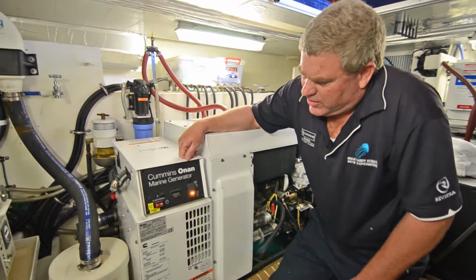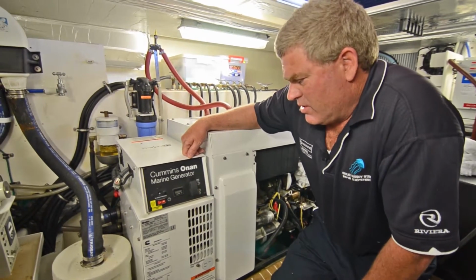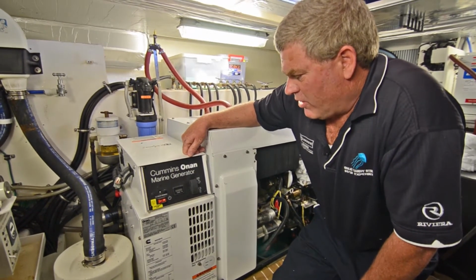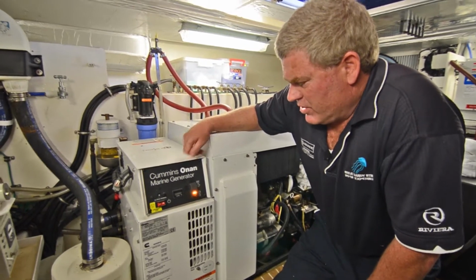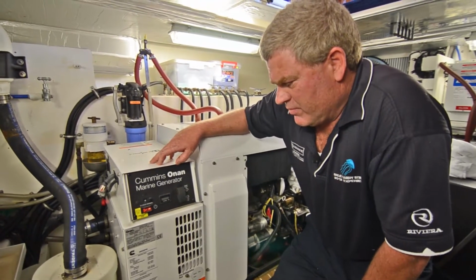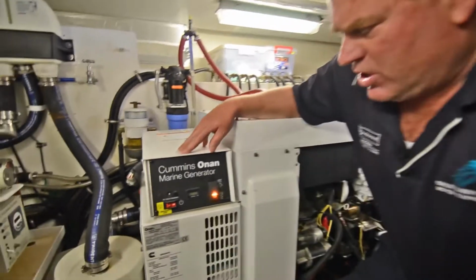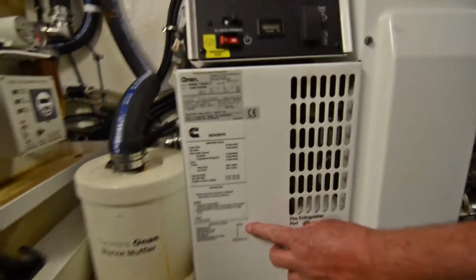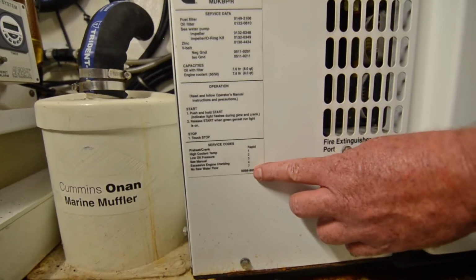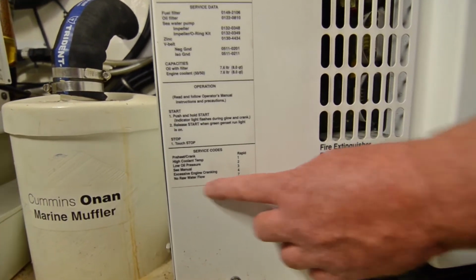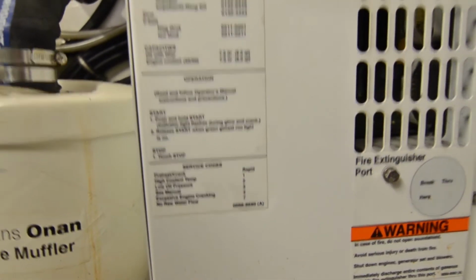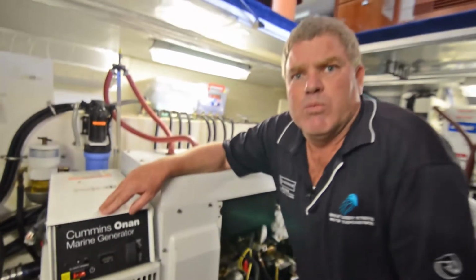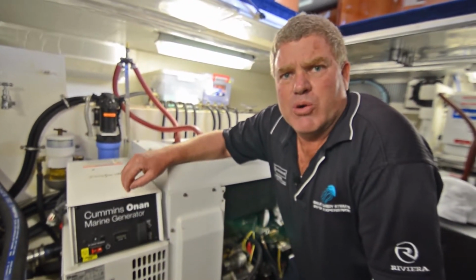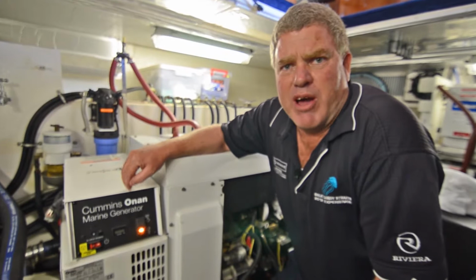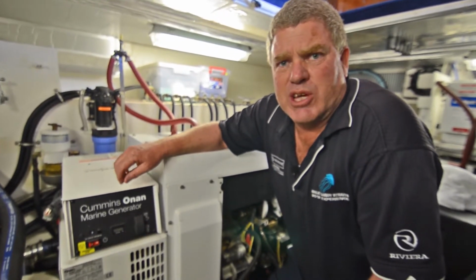Okay, so the engine's shut down, and it appears the fault code is a 7 flash indicated on the panel here. If I go down to the fault codes, number 7, 7 flashes, means no raw water. So most probably some kind of blockage or the impeller has failed. We'll check the sea strainer and then go from there.